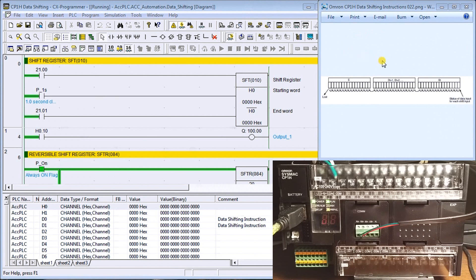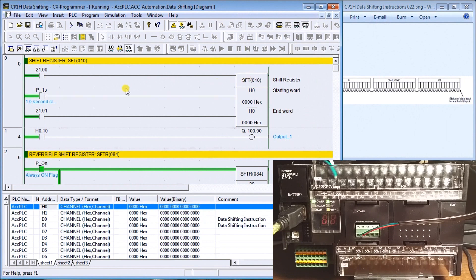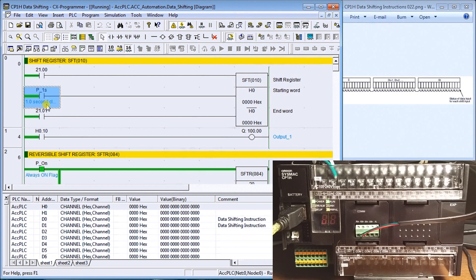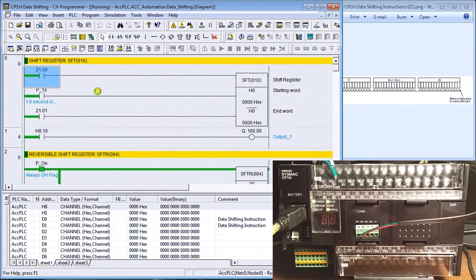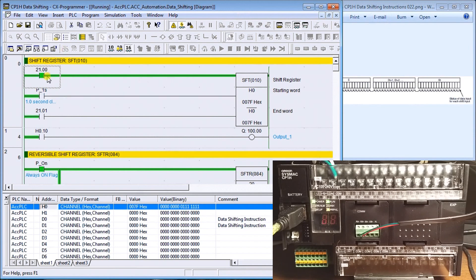Usually when we talk about data shifting, we talk about conveyor belt movement. If we sense a product on the belt, that turns a bit on, and as that bit moves along the conveyor belt we can track it within the memory word. Our first instruction is the shift register. It has a starting word and an ending word and shifts bits from start to end. In our case we're using H0 for both, so we're only dealing with the first 16 bits. Our clock pulse flag is set for one second.